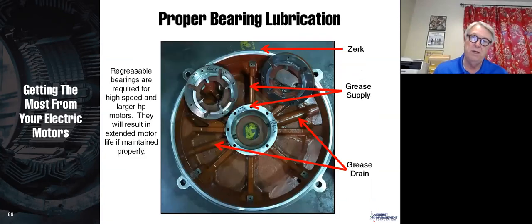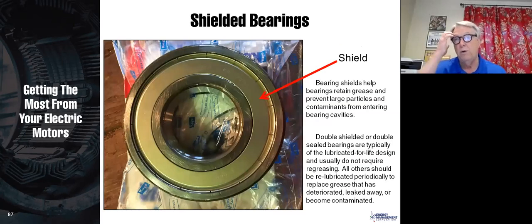Now, this is a picture of the inside of an end bell here, and you can see that here's your Zerk. When you pump, it has to go through this tube here. So when you start pumping in, it's not going into the bearing at all. It's just going through the tube that leads to the bearing. Then it goes through the bearing, and after it gets through the bearing, then it goes out the grease drain. And in this particular one, it has 2 grease drains. So make sure that those drains are open when you lubricate and open when you run the motor, and allow that grease to come out before you put the plug back on. This is a shielded bearing.